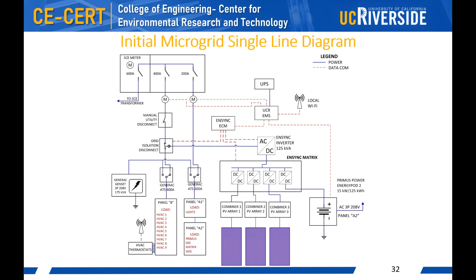There were some challenges we faced on this project. One critical challenge was that one of the companies that provided the power conversion components went out of business. Even though the system was functioning well, we were in a delicate situation where if that component failed, the microgrid would no longer be functional. So we decided, strategically, to replace that component and reconfigure the microgrid so we could be confident it would continue to function even after the end of the project.